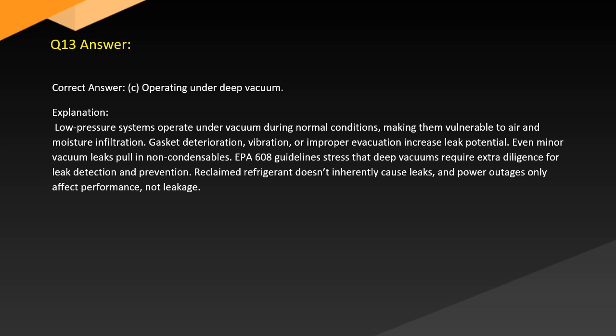Answer. Correct answer. C. Operating under deep vacuum. Explanation. Low-pressure systems operate under vacuum during normal conditions, making them vulnerable to air and moisture infiltration. Gasket deterioration, vibration, or improper evacuation increase leak potential. Even minor vacuum leaks pull in non-condensables. EPA 608 guidelines stress that deep vacuums require extra diligence for leak detection and prevention. Reclaimed refrigerant doesn't inherently cause leaks, and power outages only affect performance, not leakage.